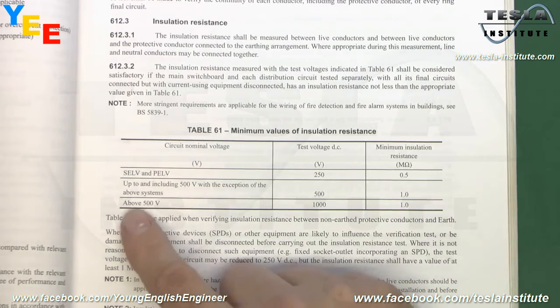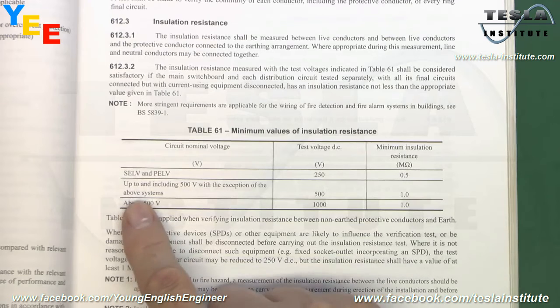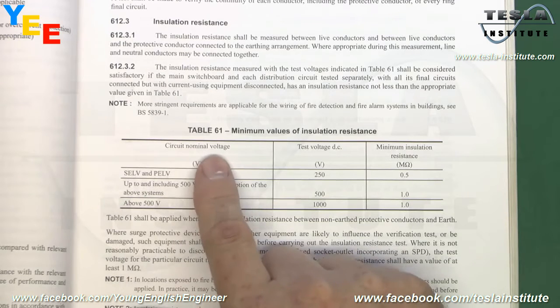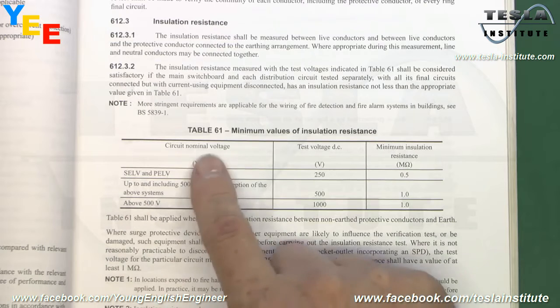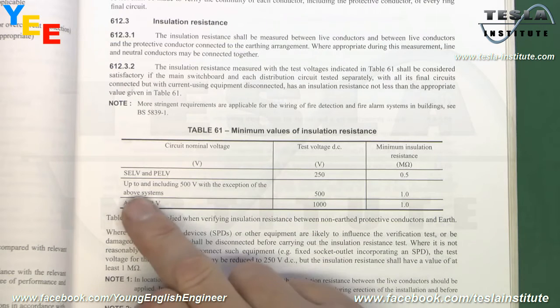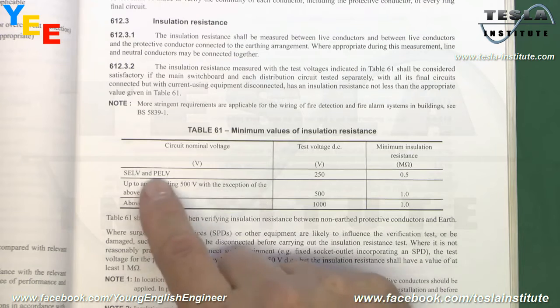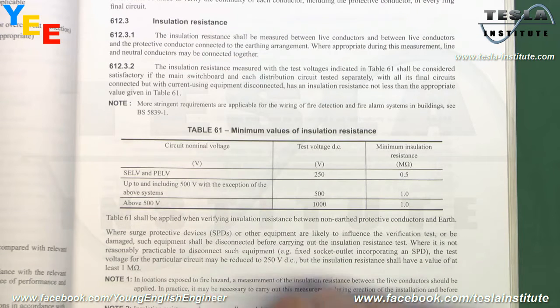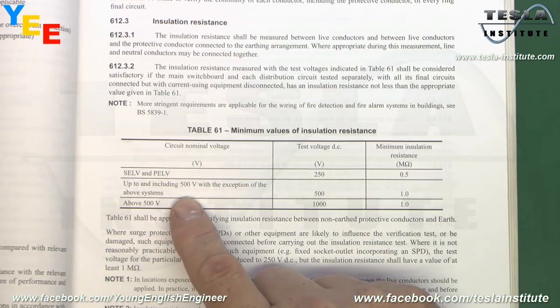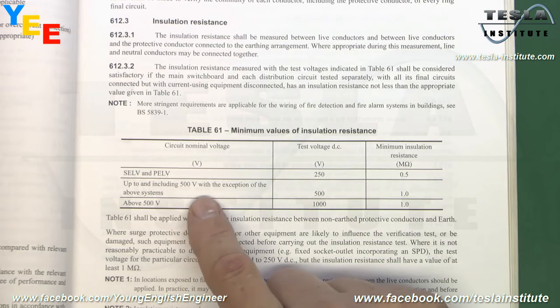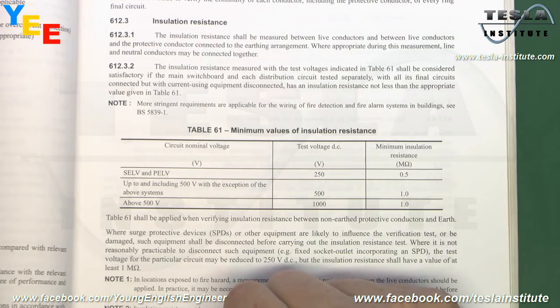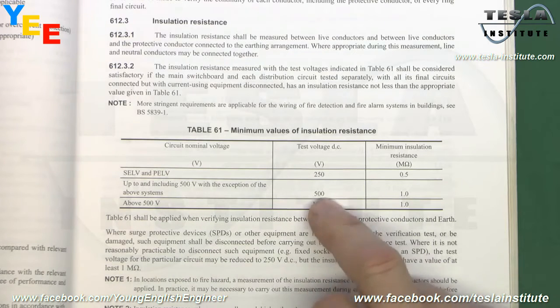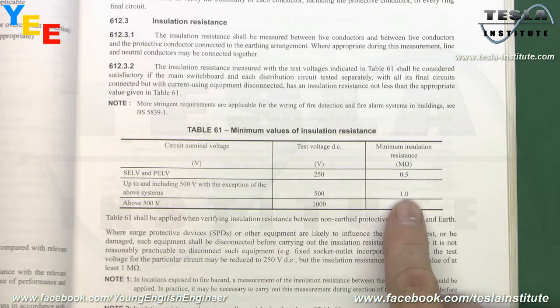I've got three choices here, and by far the most common is the middle one, which is a system with a nominal voltage on the circuit, in other words what it uses in normal operation, up to and including 500 volts, obviously with the exception of the above items. That covers your 230 volt single phase circuits and also 400 volt three-phase circuits as well. So pretty much everything you're going to find in most normal places. For that, as we said previously, a test voltage of 500 volts DC, and the minimum insulation resistance that's acceptable is 1 megohm.